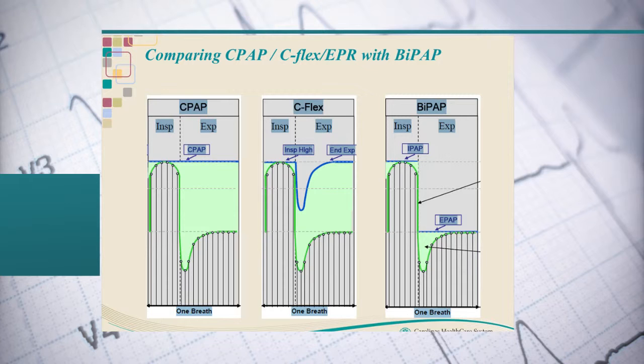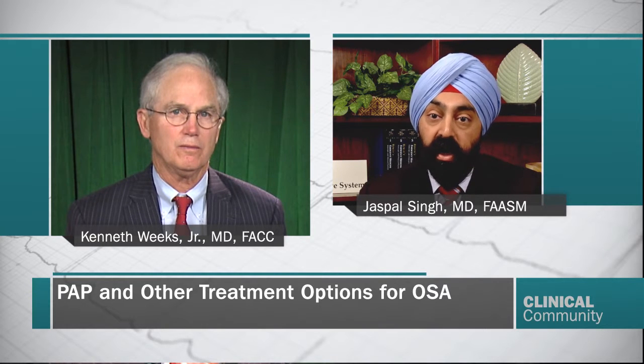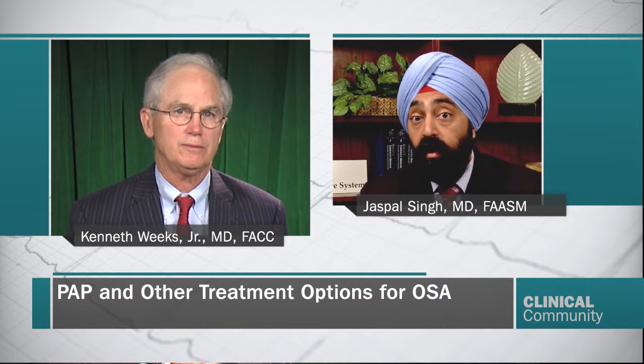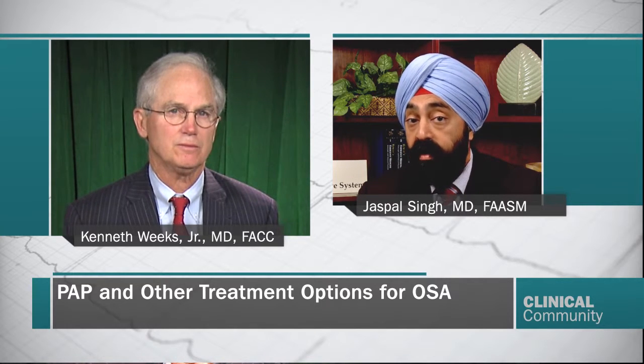That's just one advance. Another major advance has been what we call bilevel therapy, where the pressure actually changes whether you inspire or expire, and you can also set the inspiratory and expiratory pressures to automatically adjust based on the device's read of airway mechanics. This latter advance, or the auto component of this, has really undergone some major advances recently, and it's pretty amazing now that the CPAP devices can self-adjust and sense if a patient's airway is not being well treated or not being well opened, and adjust the amount of air delivery. And it can also lower it when less air is needed. A lot of my patients find that very comfortable and very comforting to know that they're not getting more air than they need at given times.